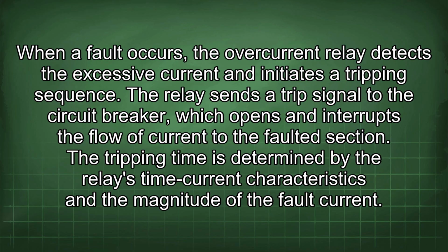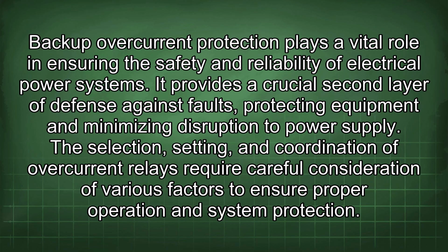When a fault occurs, the overcurrent relay detects the excessive current and initiates a tripping sequence. The relay sends a trip signal to the circuit breaker, which opens and interrupts the flow of current to the faulted section. The tripping time is determined by the relay's time current characteristics and the magnitude of the fault current. Backup overcurrent protection plays a vital role in ensuring the safety and reliability of electrical power systems. It provides a crucial second layer of defense against faults, protecting equipment and minimizing disruption to power supply. The selection, setting, and coordination of overcurrent relays require careful consideration of various factors to ensure proper operation and system protection.